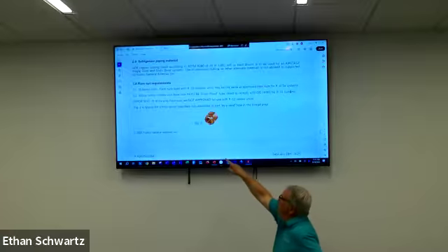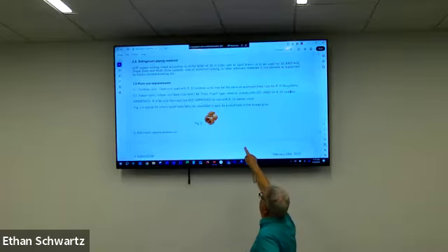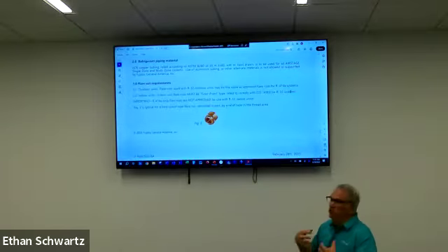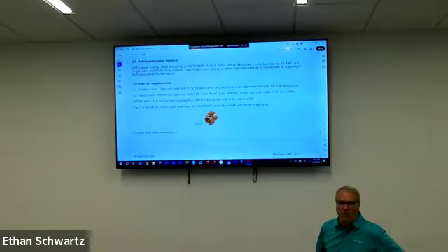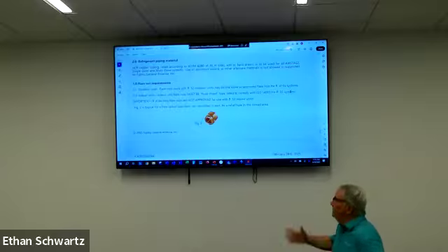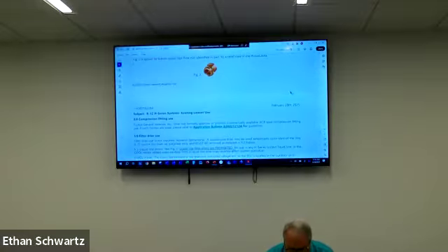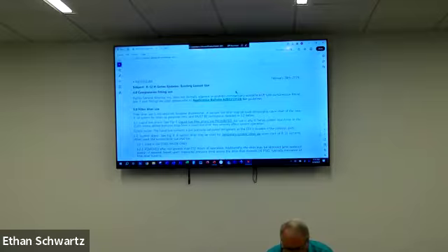I guess there's something with R32 and frost, but the note right there says R410A-only flare nuts are not approved for use on R32 indoor units. So you've got to make sure you use our flare nuts that come with our R32, because they have those frost relief holes. Those ship with the units? They should, yes. But that's one of those little nuances that if you don't come to training, you don't know. And of course, compression fitting use is all right. We've got a bulletin on that if you want to look at it.